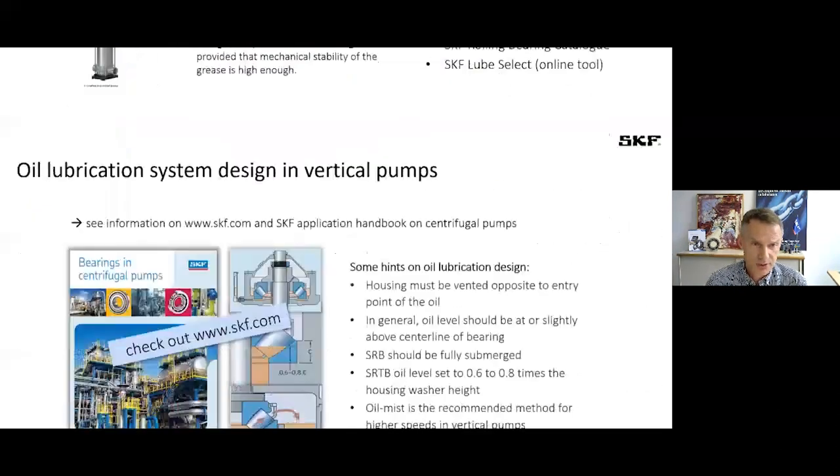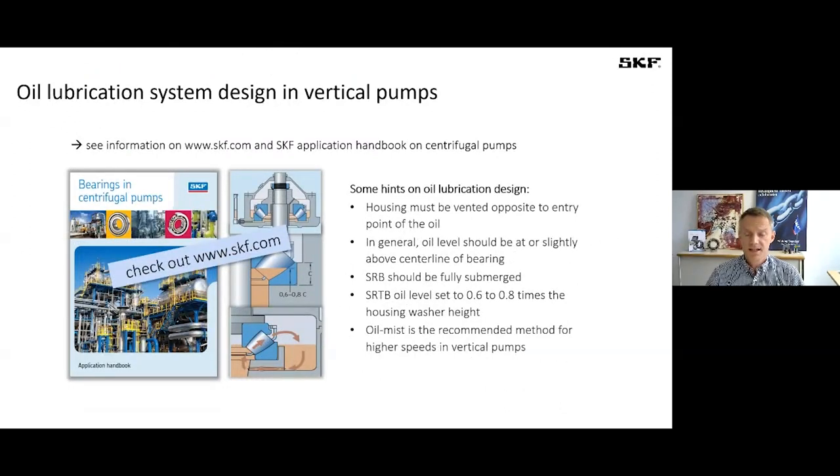When it comes to oil lubrication for vertical pumps, SKF has a lot of good hints also in the material. So again here, check out either the bearing pump handbook or SKF.com. Depending on the bearing type, like for example this spherical roller thrust bearing here on the screen, you will find information how to design the oil flow and the oil level. Note also that these type of bearings, they have a kind of pumping function. We will see that later on in an example.